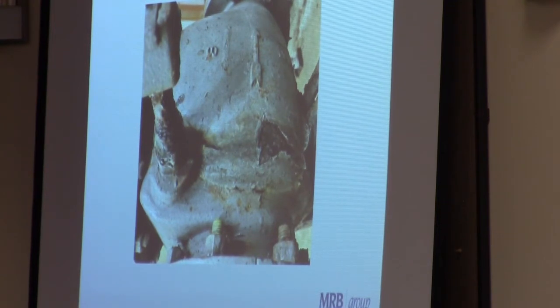Are those, at that pump station, are all 3 pumps designed to be running at the same time, or is one generally for backup? Okay. Yeah, go ahead. So normally, the pump station with 3 pumps, lead, lag, and standby. Right now, and actually, it's been for quite a while, we have a lead and lag. We do not have a standby. During high flows, you'll have 2 pumps kick on, and if needed, 3. Obviously, if you're getting to 3, we're in trouble. If you're getting to 2, quite honestly, in my opinion, you've got some high flows.